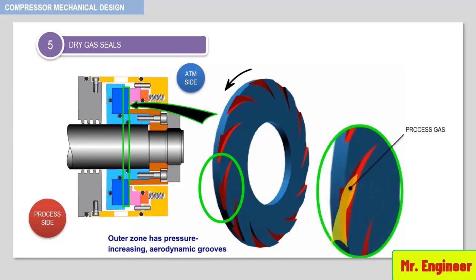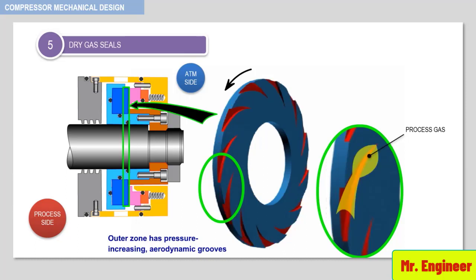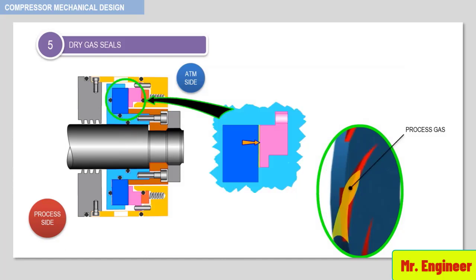These grooves compress the incoming gas as the shaft and rotating seat rotate, and are arranged on the high-pressure side of the seal in order to achieve the necessary pumping effect. The buildup of pressure in the sealing gap results in the formation of a stable gas film, as depicted here.